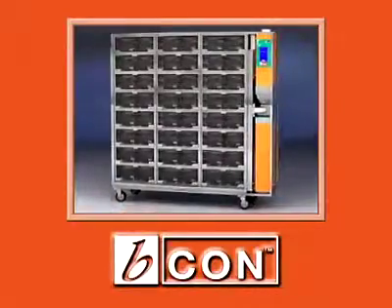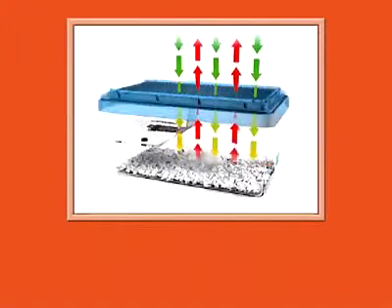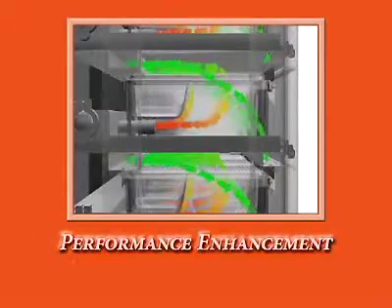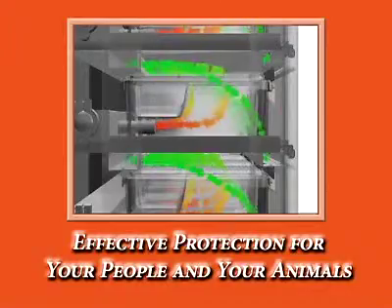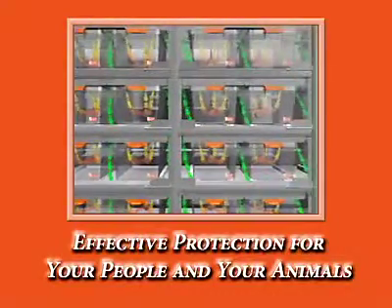A completely revolutionary design, the Beacon Biocontainment System provides a simple and reliable housing solution for ABSL-3 facilities. For decades, the most widely used type of mouse cage for ABSL-3 has been the static micro isolator. Effective ventilated biocontainment housing represents a significant performance enhancement. Beacon is a negative cage within a controlled environment cabinet, creating a containment system made up of three separate zones.